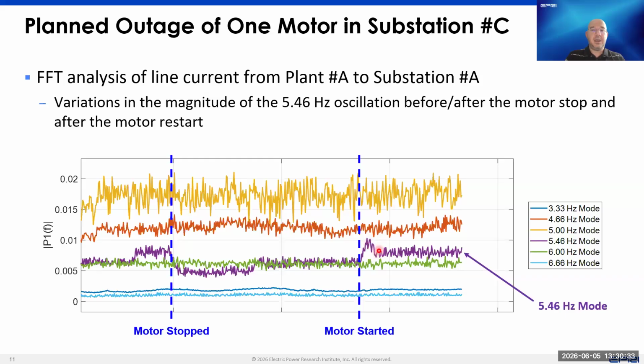And then probably at this point, there were still some updates or rescheduling of the loading of the different motors within the substation. And eventually we got back into a steady state. So that was also an interesting data set that we studied, showing how the energy level of that oscillation mode, specifically at that 5.46 hertz, which is associated with the motors' specific speed and RPM, changed as motors were stopped and restarted and the schedule of other motors in service was adjusted.